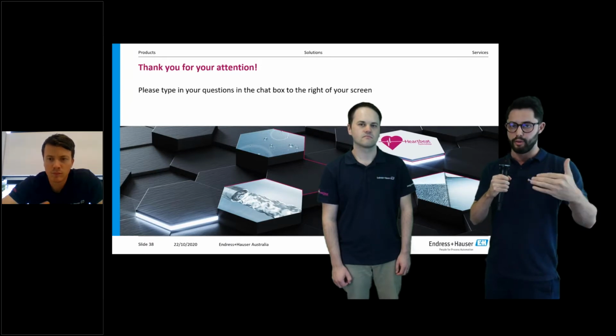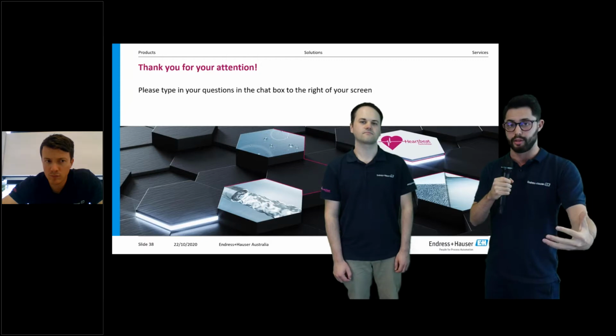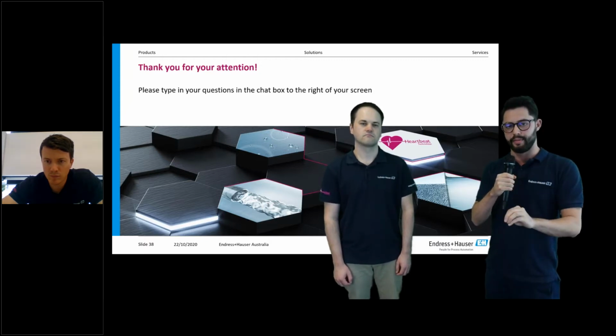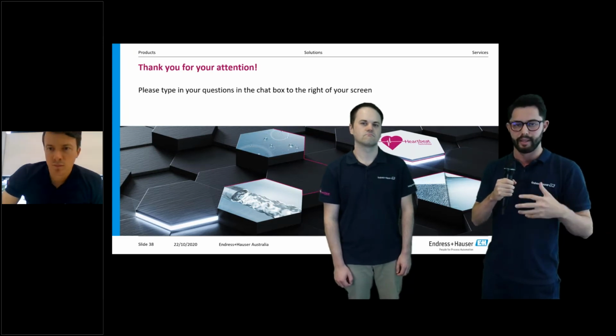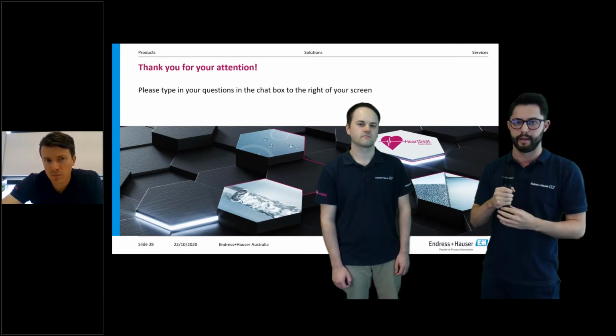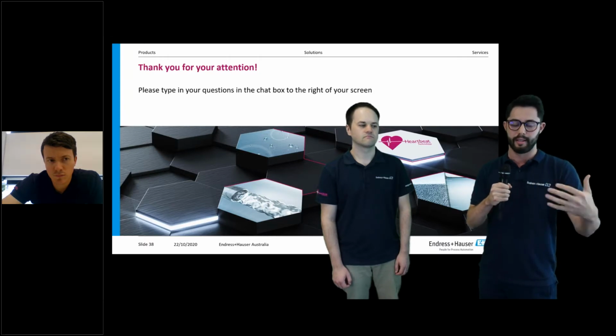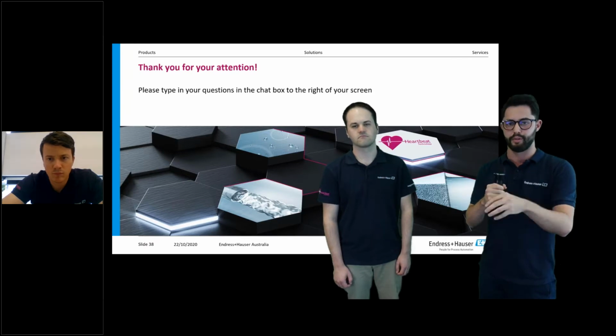You can use it, as I said, as a resource to optimize and reduce your costs. But the idea is not to replace the calibration with a verification. It also depends on the criticality of your device and internal compliances. So it's mainly up to the customer to decide if the verification is enough for them, or if they really need a metrological aspect to that measuring point.